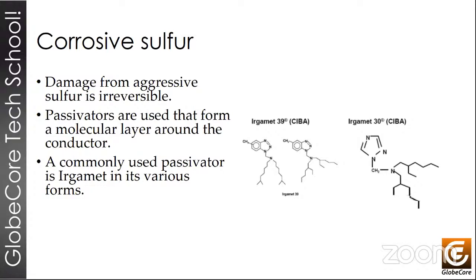Irgamet is one of the most widely used chemicals, and is usually diluted in a proportion to produce a concentration of about 100 ppm. It forms a very thin sheet on the copper, which acts as a protective barrier between the copper and the oil. This process of adding chemicals for passivation is continuous, because the concentration of the passivator drops over time, and any value below 25 ppm means that we basically have no protection anymore. Next slide, please.